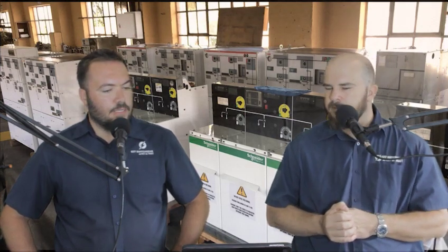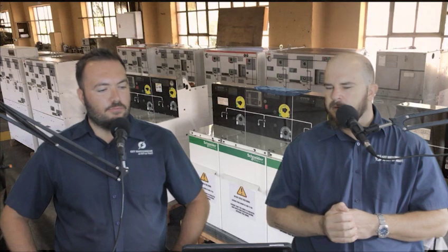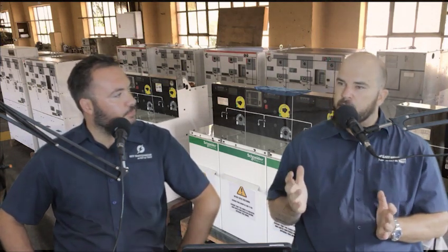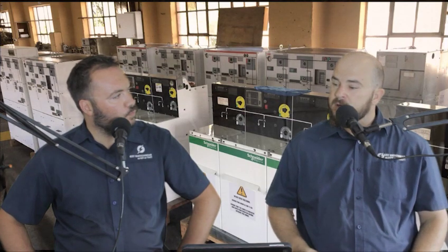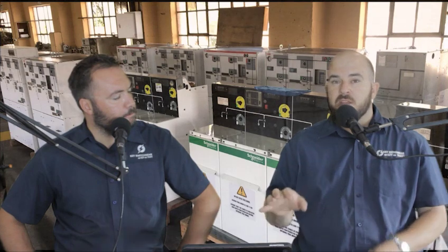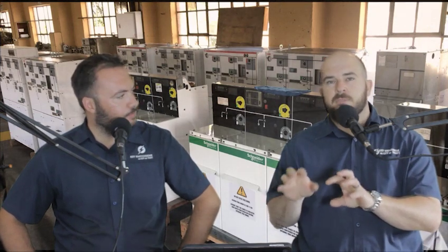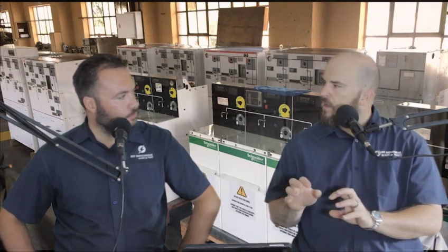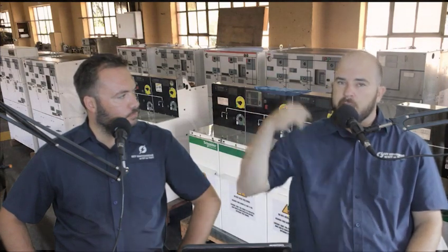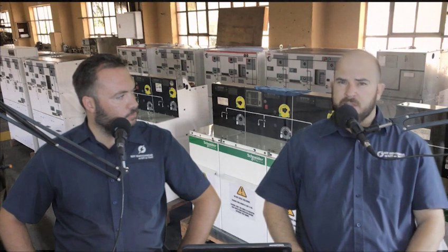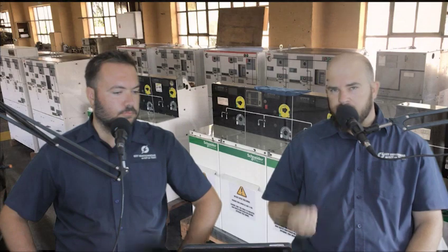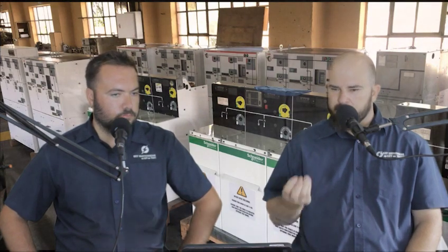Okay, cool. And then tell us more about the different types of cable compartments and the designs thereof. Cable compartments are quite interesting. It is where your cable comes in and connects onto your switchgear. There you have your bushings, which is the place where your cable connects. You have top entry and bottom entry as the two options of where the cable comes in. Most of the time, 99% of the usage would be bottom cable entry, so the cable is coming from the bottom.